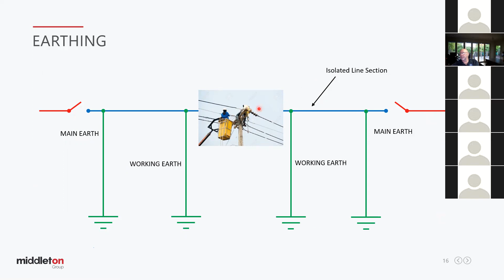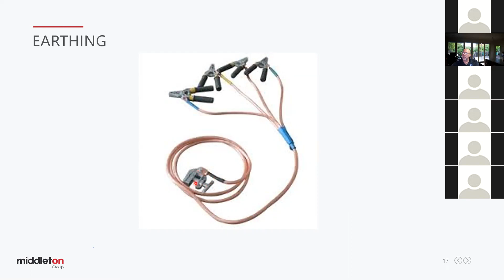Now on overhead lines, you'll use equipment like this. Portable or trailing earth, you can see that's a trident arrangement. In fact, there's 4 on there, and a clamp on the bottom that can be applied to a structure. I was very familiar with this sort of arrangement, not with 4 but with 3. This would be a low voltage style earth with 4 conductors. Stobie poles make great earth stakes, so you just need a clamp like this towards the top of the pole and you've earthed your conductors.